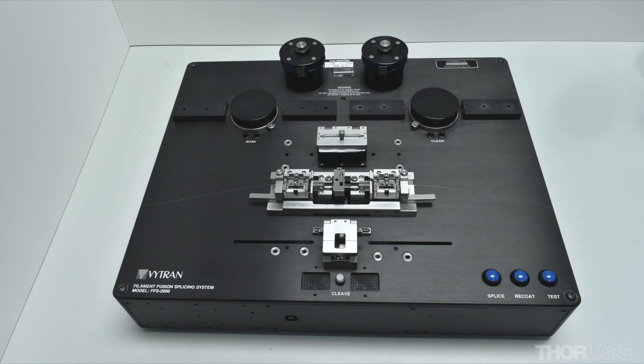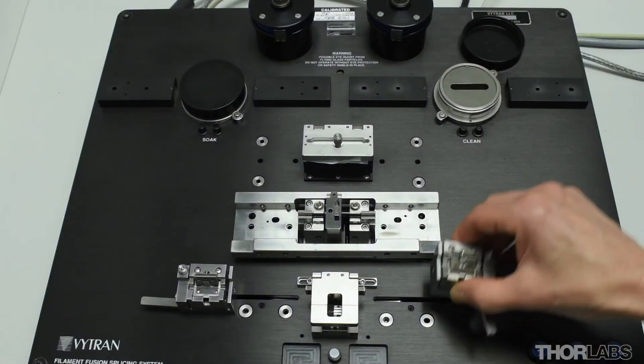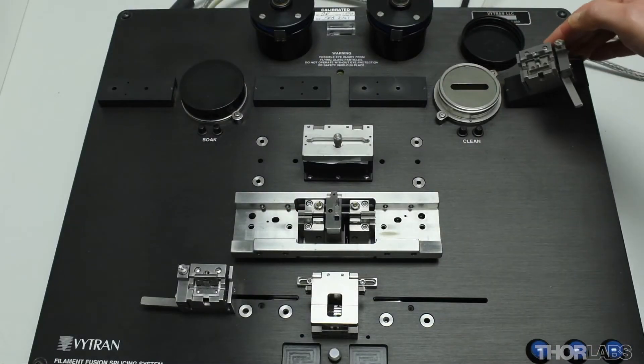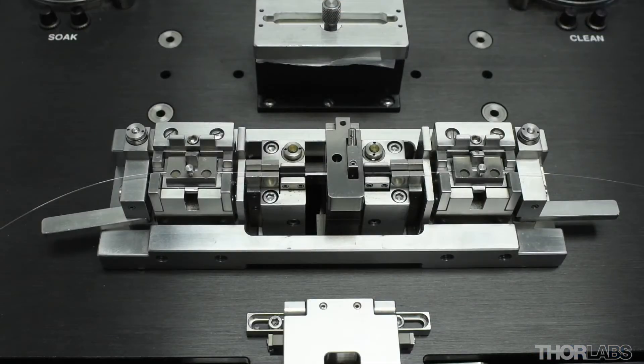The FFS2000 unit has been designed to minimise fibre handling and contact with the glass surface of the fibre. Fibre holding blocks are used to transfer the stripped fibres around the unit and the splice is carried out in an inert argon environment that minimises contamination.